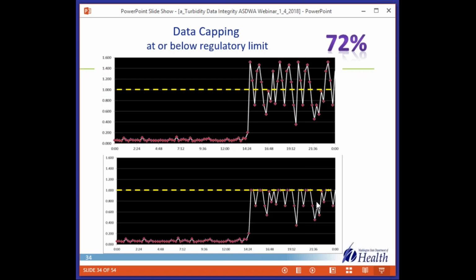We found 72% of those systems, or 18 systems, had signal span set to cap the maximum turbidity sent to the SCADA system or the recording device at a level below the regulatory limit. Most of these cases, they were set to 1.0 NTU, but we also had one set at 0.5 and another at 0.6 NTU. So that's not so good.